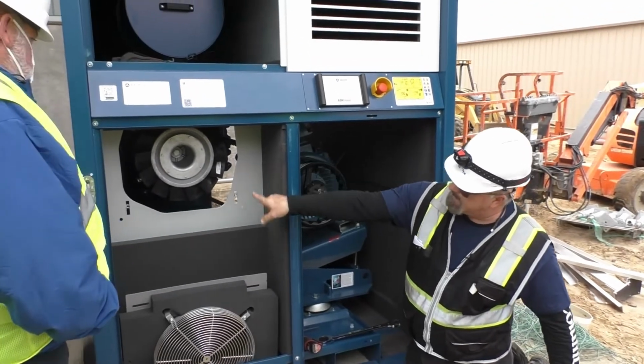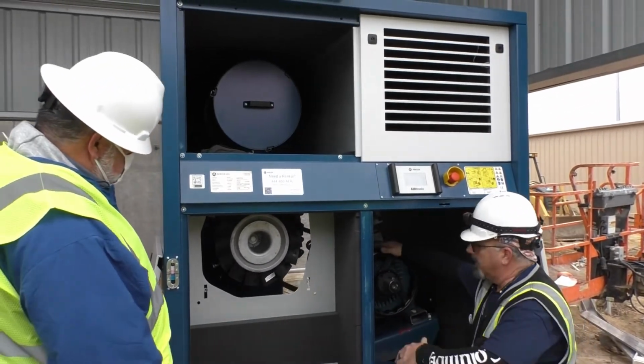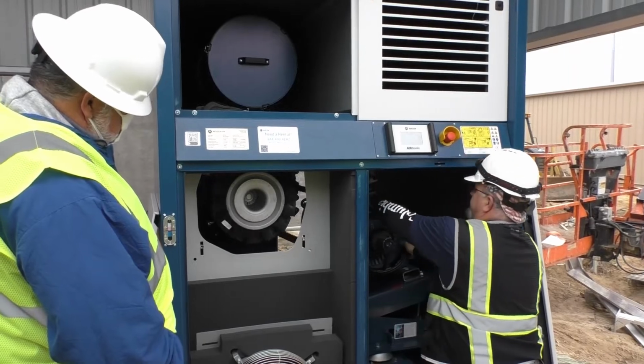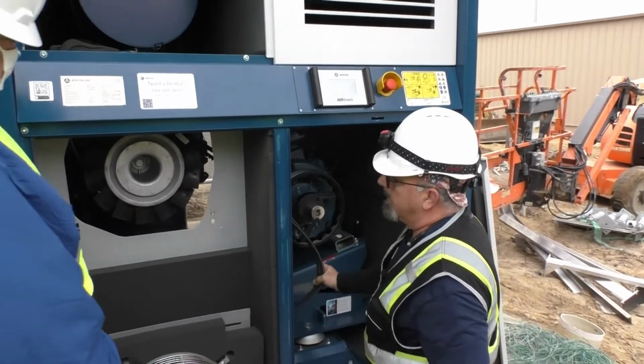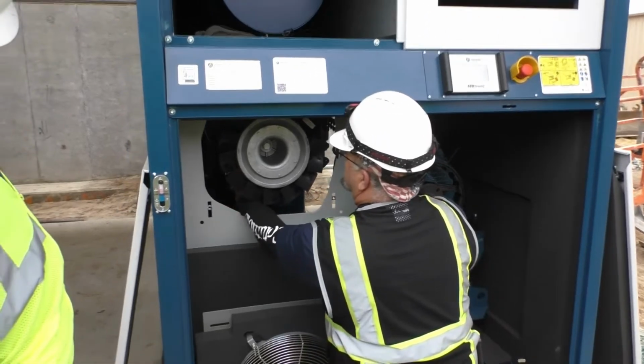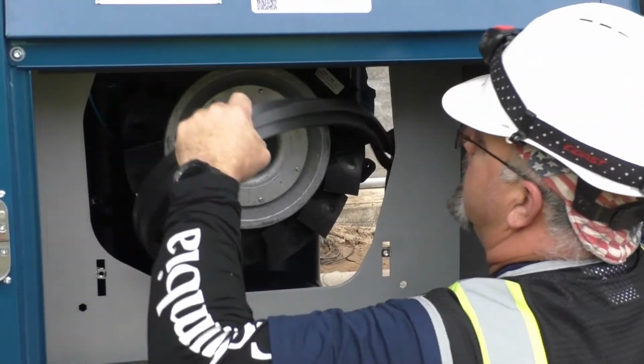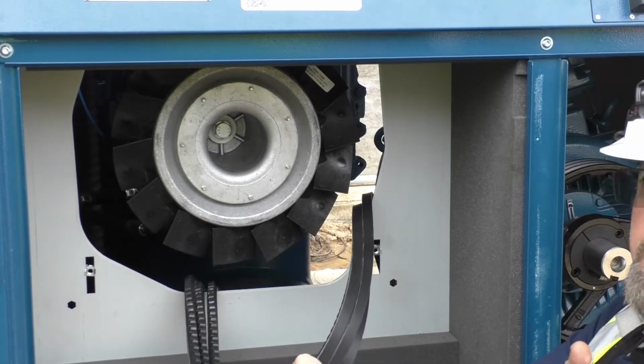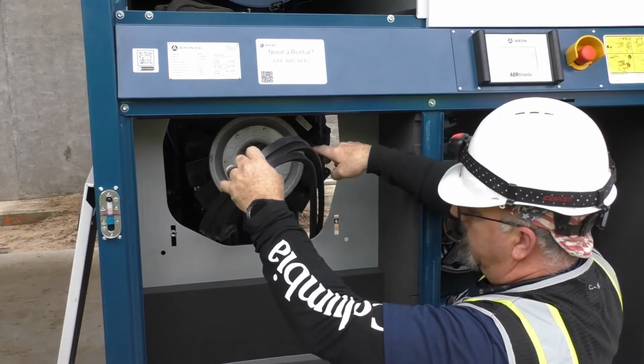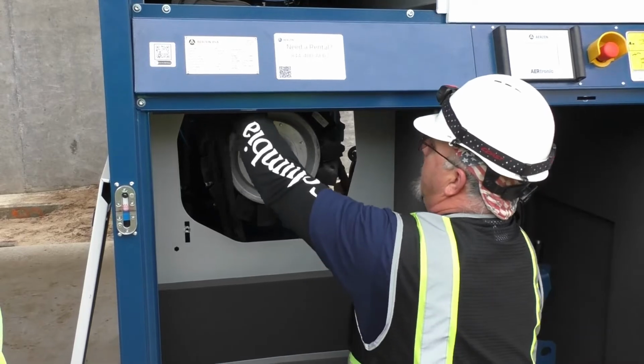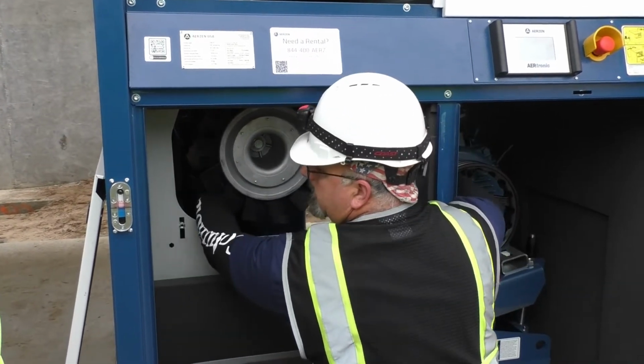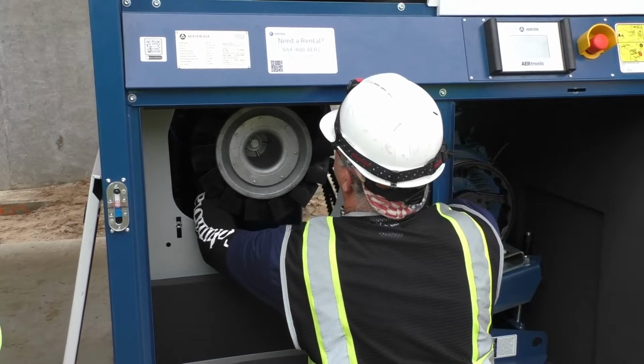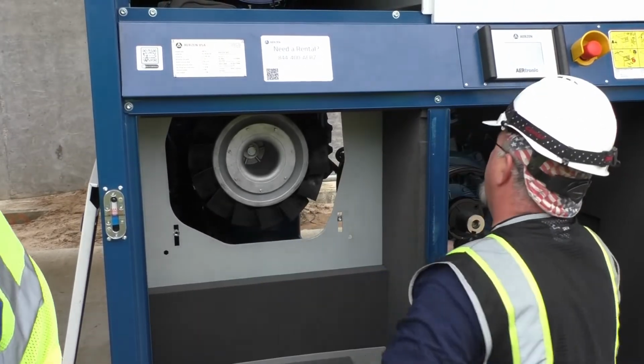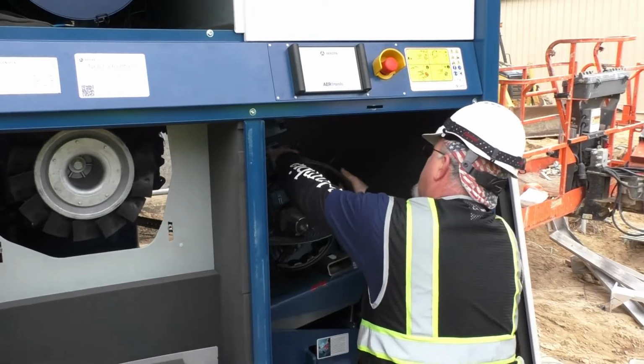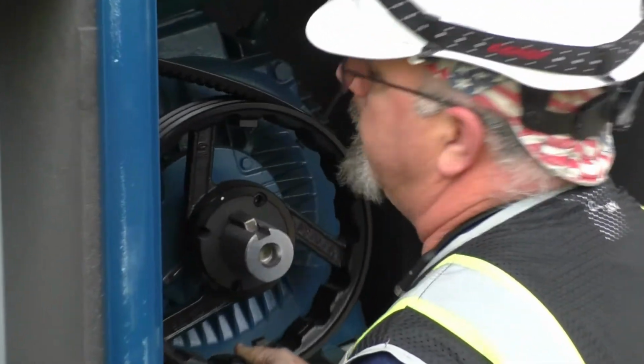So once you've raised the guard off, that allows you access around the fan. So you raise it up high enough to get your belts off. You roll them off. You come over here. You take them out. Take your old ones out. You put your new ones in just like you took these out. Make sure when you put them in, you line them up on the grooves for the pulley. And then once you do that, you put them back on.